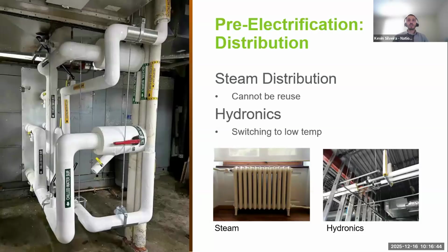So looking at your distribution systems, it's very important, if replacing them, to go to low temperatures. So say you have a building with steam distribution, and the distribution is over 100 years old. There's really not much we can do to utilize that system when converting to a heat pump system. However, when we're looking at hydronic systems, there could be opportunity to switch those over to low temperature systems. For example, you're in a school and your unit ventilators are failing. Switching out those unit ventilators to low temperature unit ventilators is possible and makes it much easier in the future to switch over to something like an air to water heat pump.